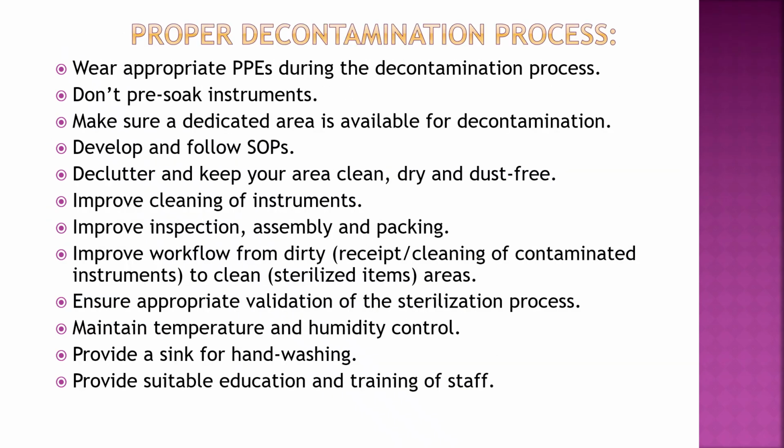Now the proper decontamination process. Wear appropriate personal protective equipment like gloves, apron, face mask, cap during the decontamination process. Don't pre-soak instruments. Make sure a dedicated area is available for decontamination, and follow standard SOPs. Then there should be regular monitoring of temperature, humidity control, and a sink for hand washing. Provide suitable education and training to the staff.